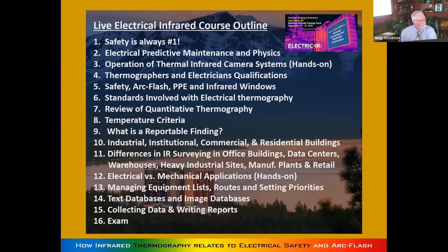But let's talk practical stuff. You're 4 or 5 feet away from a panel with a 320 by 240 camera, you're getting plenty good spatial resolution to measure the high temperature. We're not doing a scientific experiment trying to measure one pixel. So the answer is maybe 3 feet with a 320 camera and 4 feet with a 640 camera.